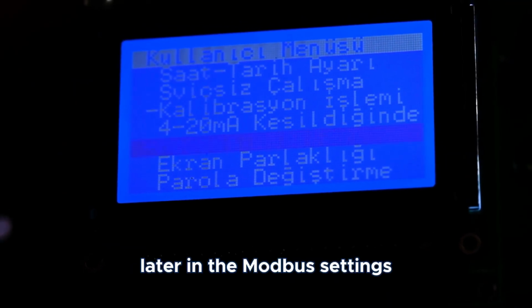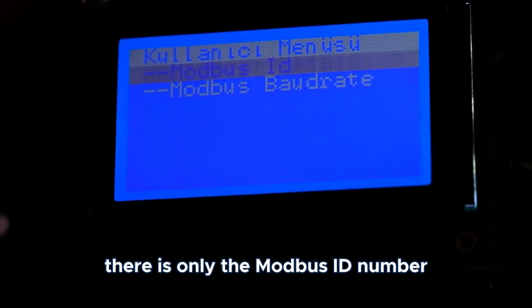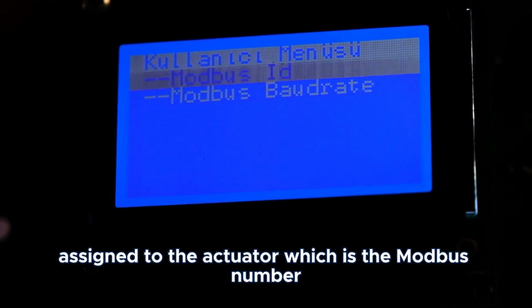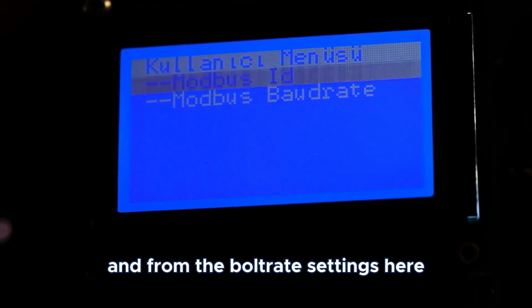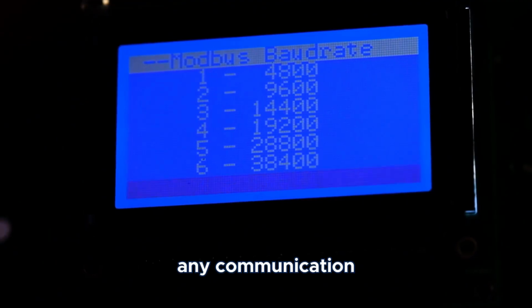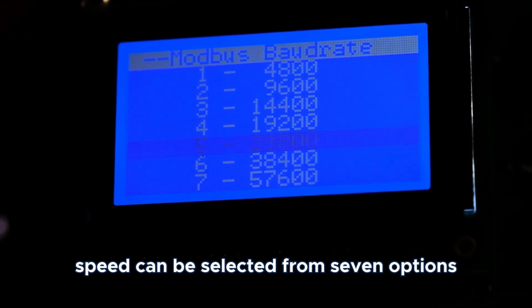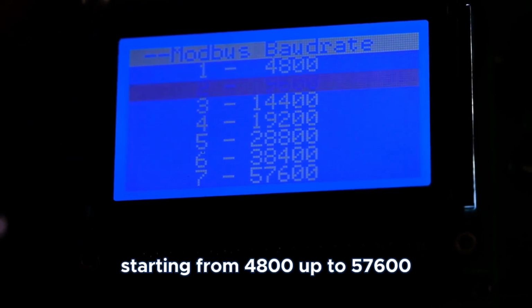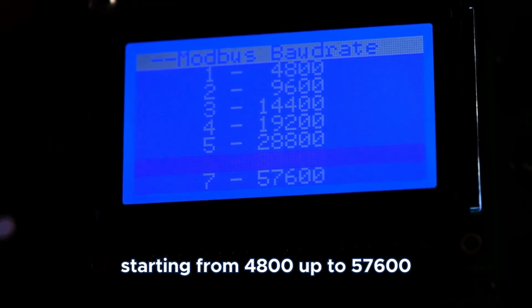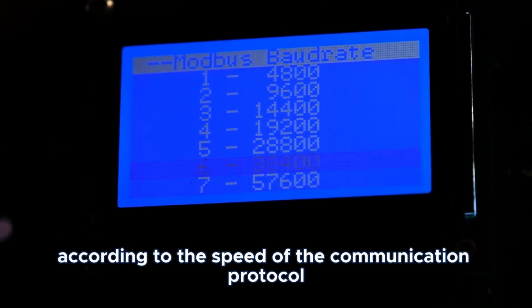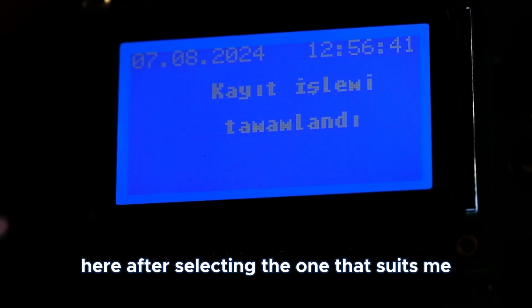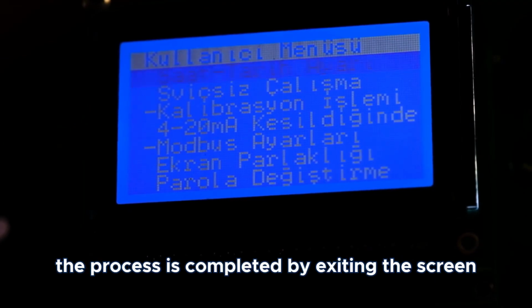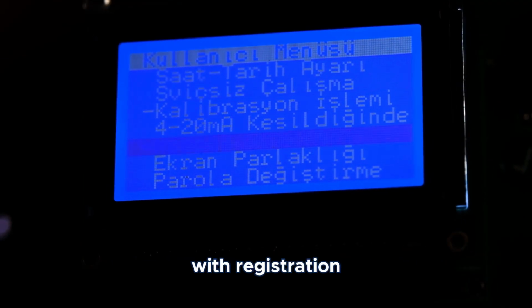Later, in the Modbus settings, there is only the Modbus ID number assigned to the actuator, which is the Modbus number, and from the baud rate settings here, any communication speed can be selected from 7 options, starting from 4800 up to 57600, according to the speed of the communication protocol. Here, after selecting the one that suits me, the process is completed by exiting the screen with registration.